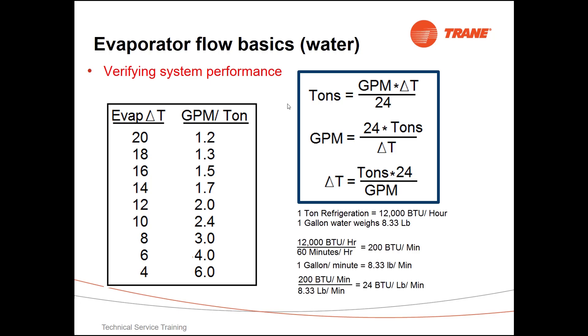Once you know what your gallons per minute flow is through the chiller, then we can run this formula — GPM times delta T divided by 24 — to determine how many tons that machine is actually doing.